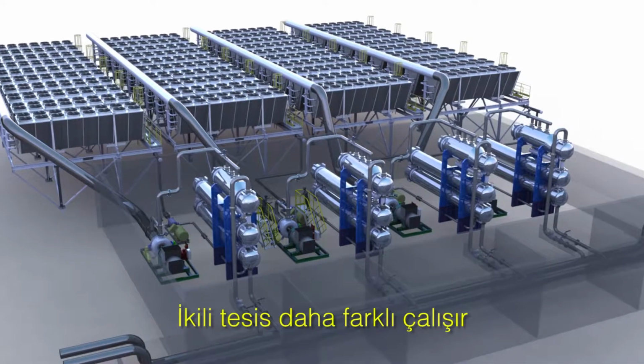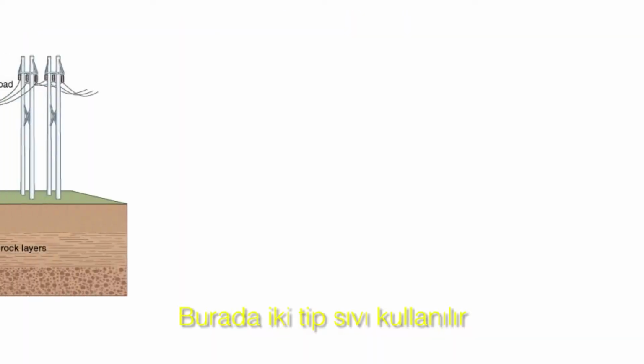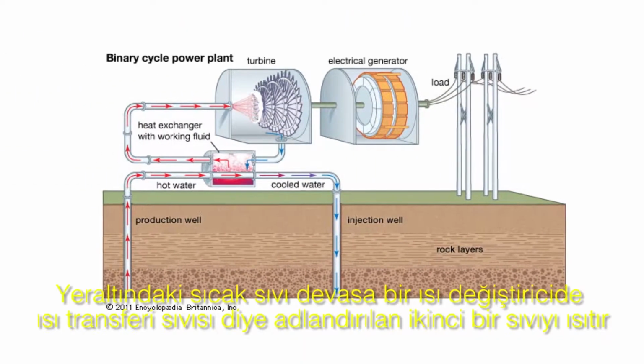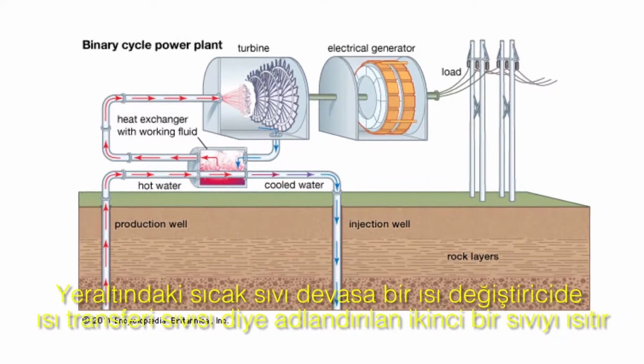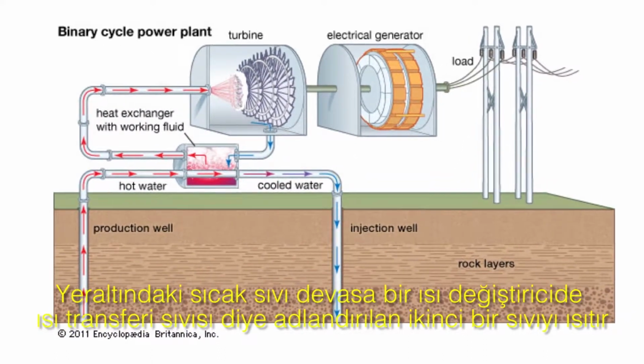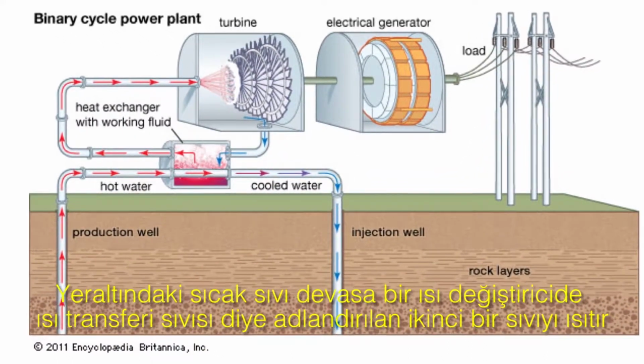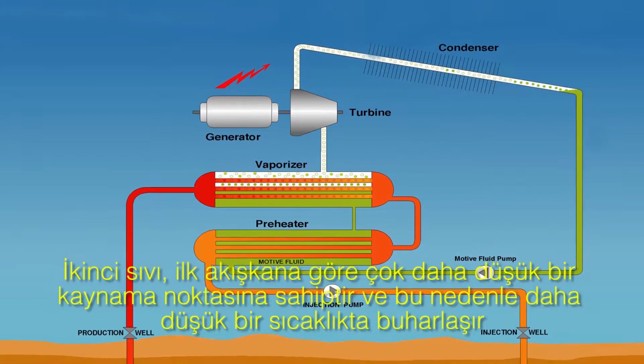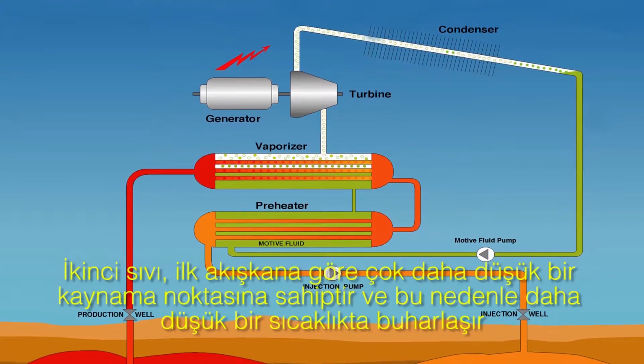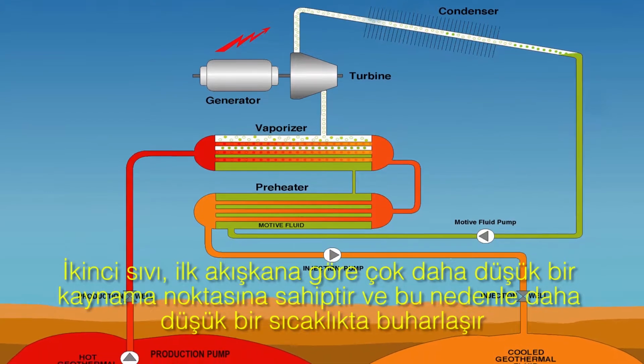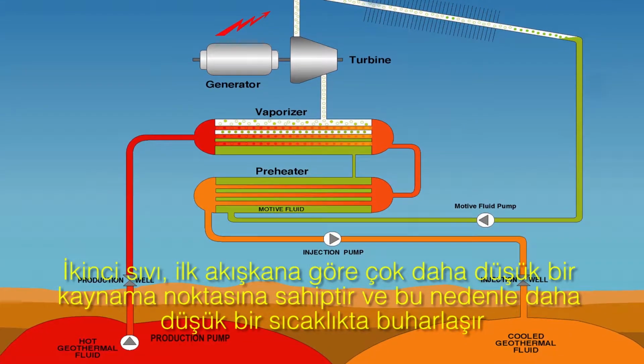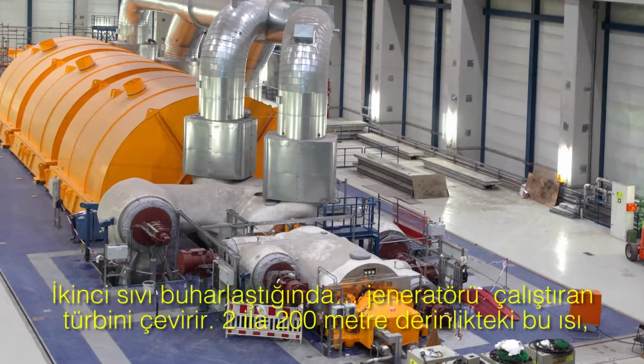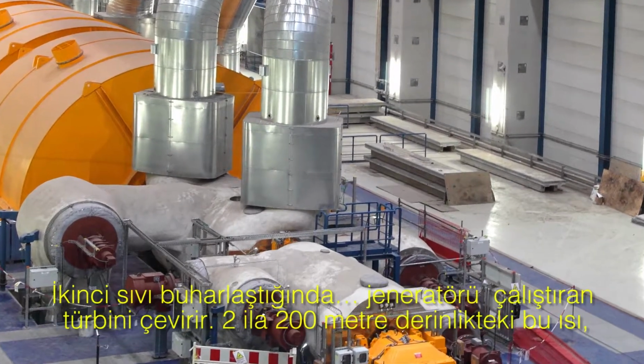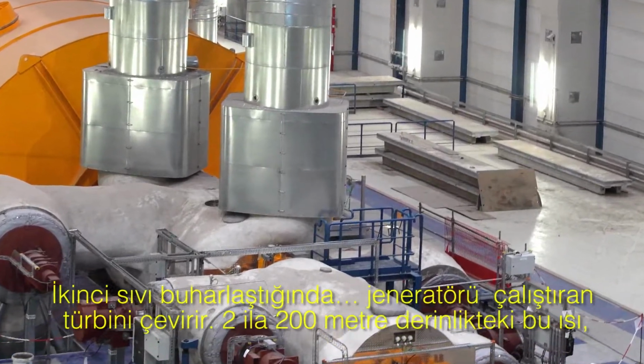A binary plant works differently. It uses two types of fluid. Hot fluid from underground heats a second fluid, called a heat transfer fluid, in a giant heat exchanger. The second fluid has a much lower boiling point than the first fluid, and so it flashes into steam at a lower temperature. When the second fluid flashes, it spins a turbine that drives a generator.